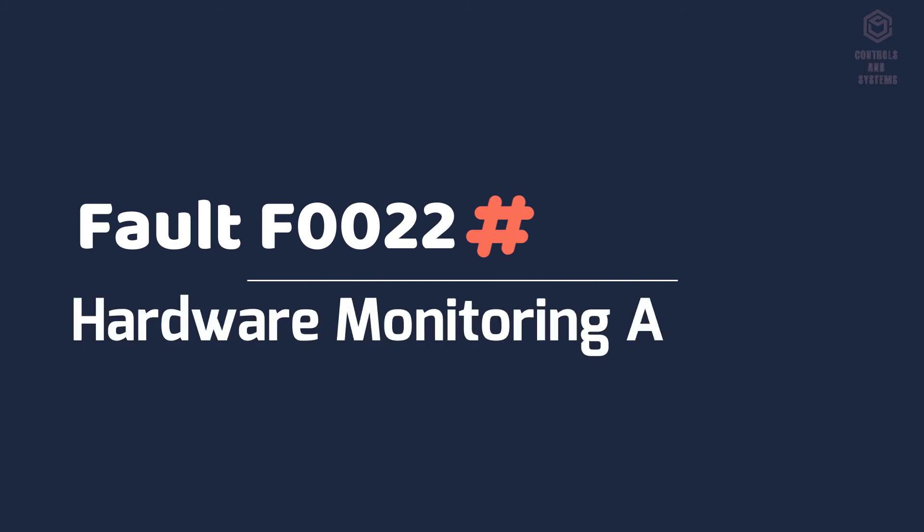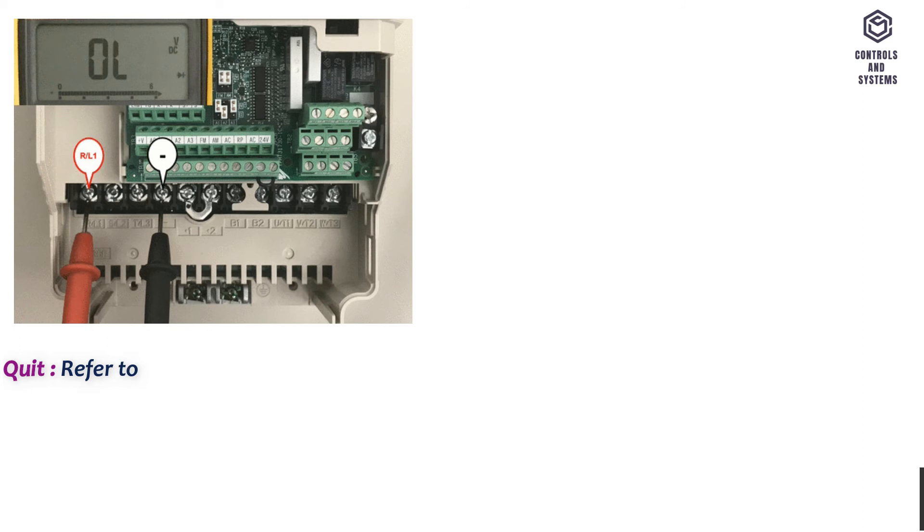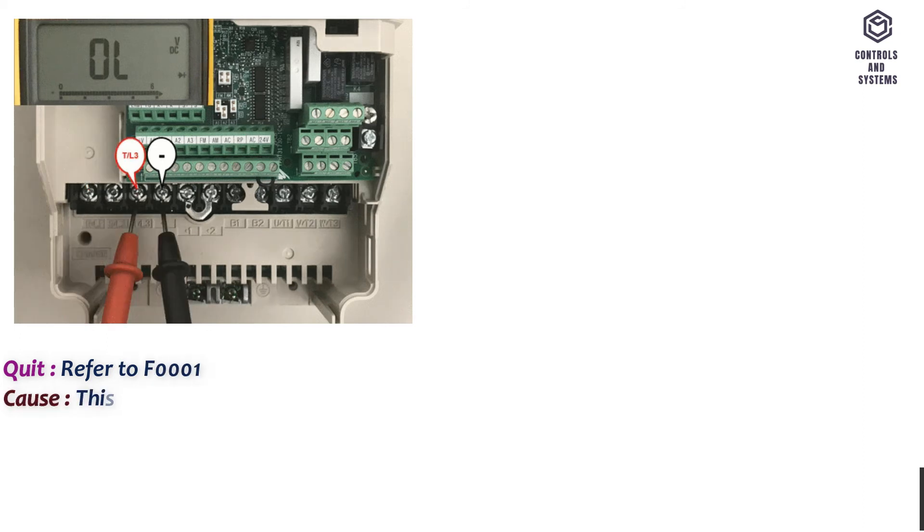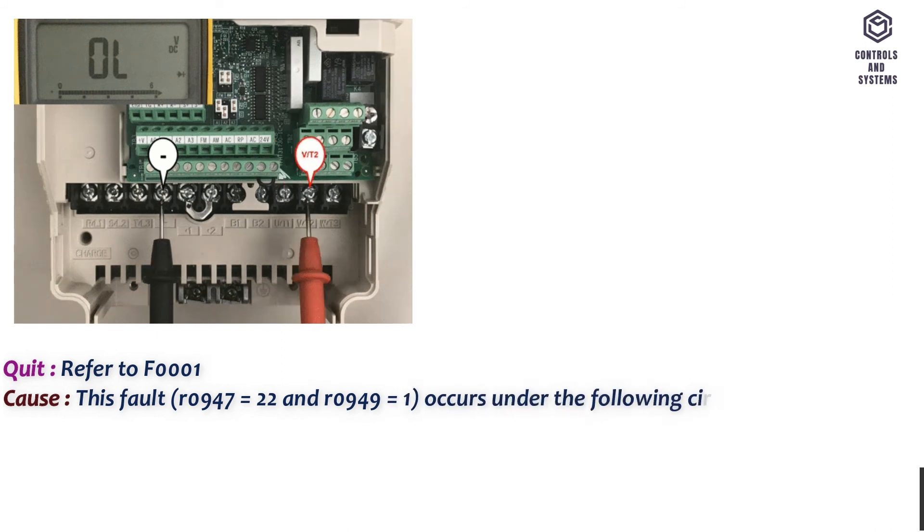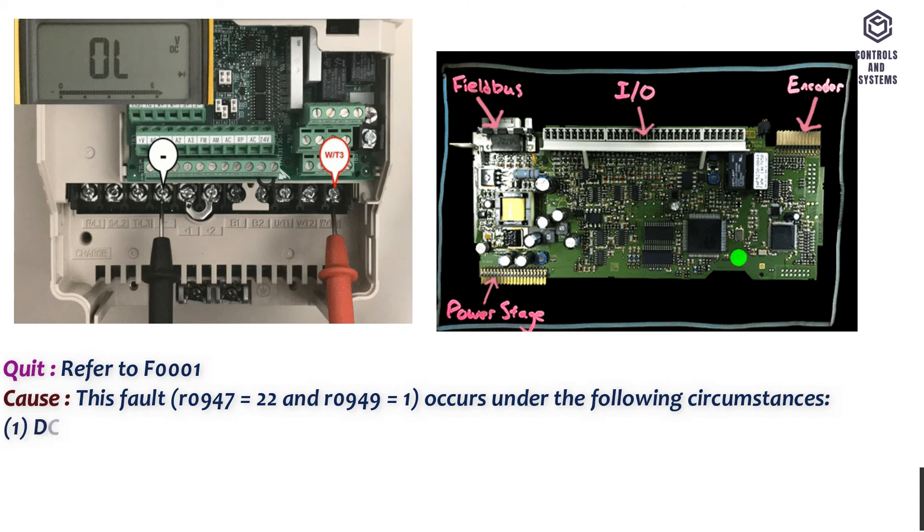Fault F0022 hardware monitoring active. Quit: Refer to F0001. Cause: This fault R0947 equals 22 and R0949 equals 1 occurs under the following circumstances.